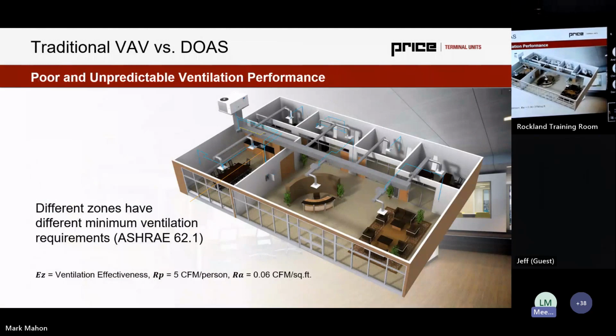And so the way I want to frame poor and unpredictable ventilation performance and what ASHRAE means comes from this example, which is a reworked example with some calculations that maybe are more applicable to common applications, but it comes from the DOAS Fundamentals Handbook. So we have an open office environment here with our facade at the bottom of the screen, internal zones at the top. It's a bit of a snapshot. We can imagine this as a particular portion of a larger tenant fit out project or something like that.